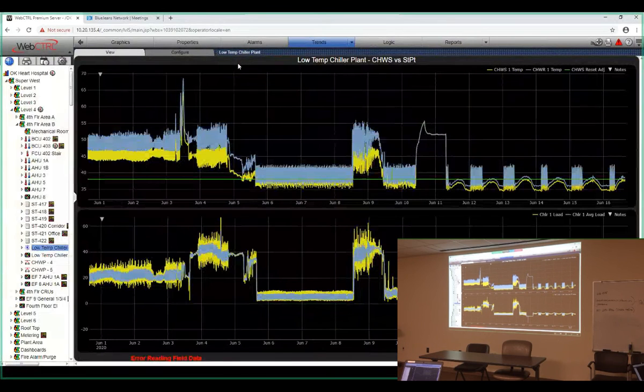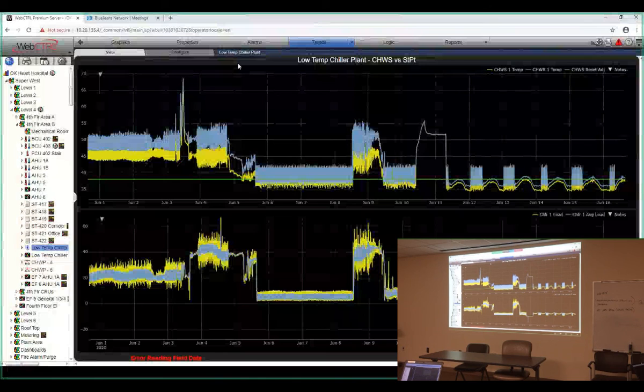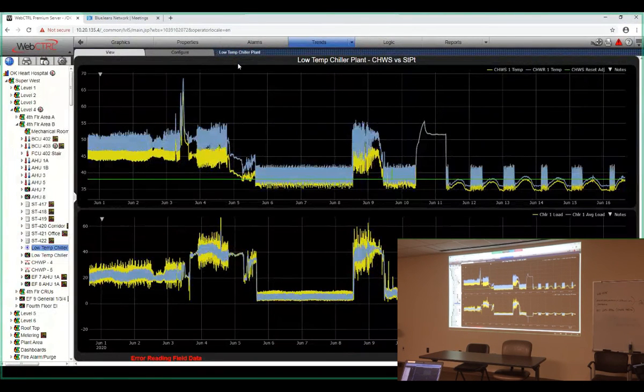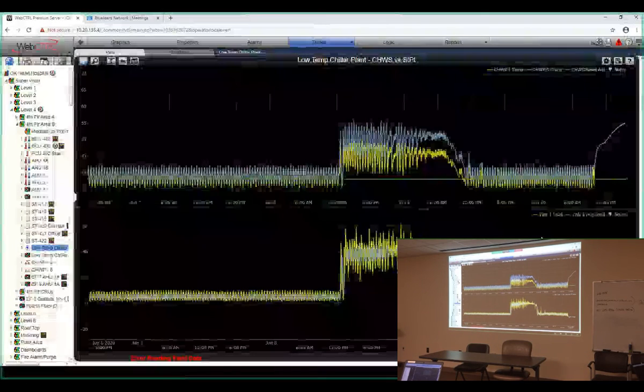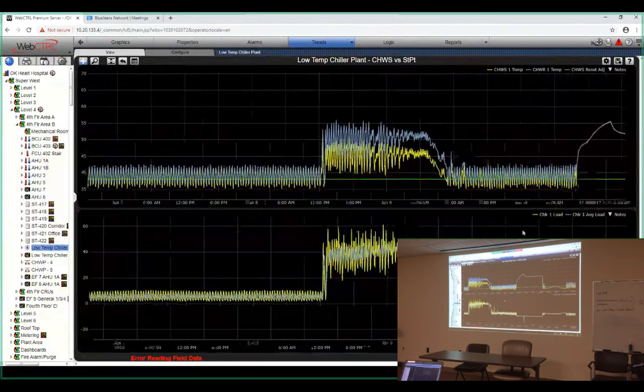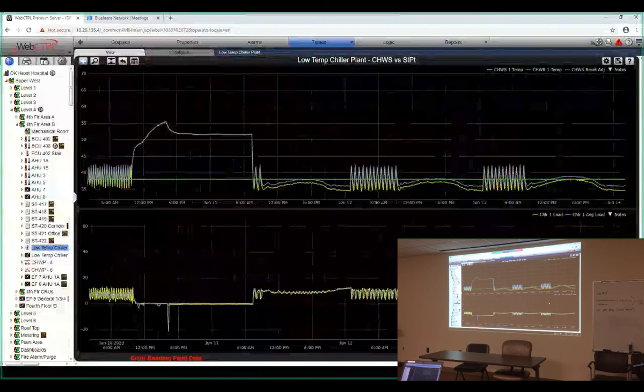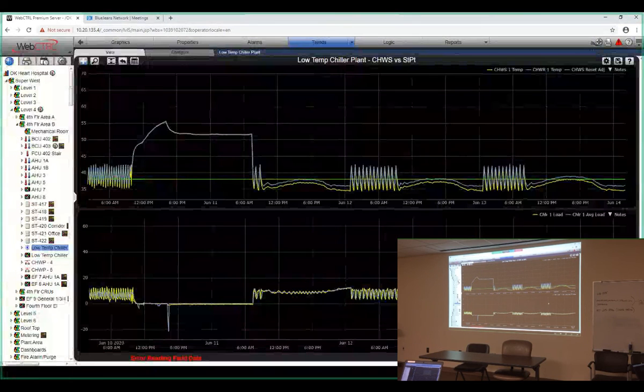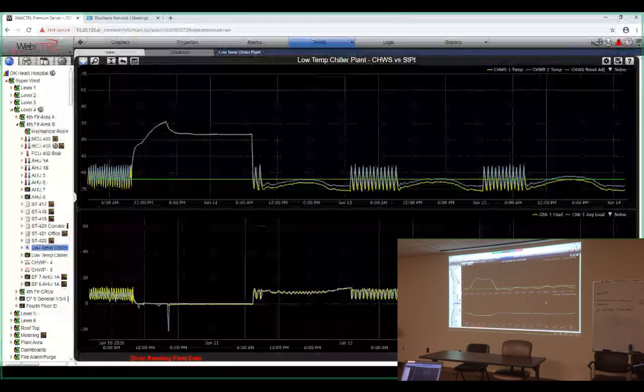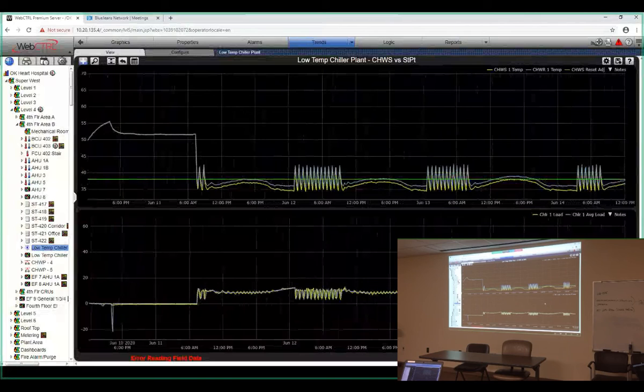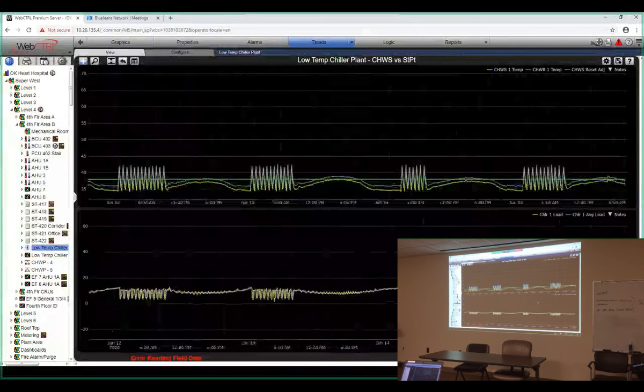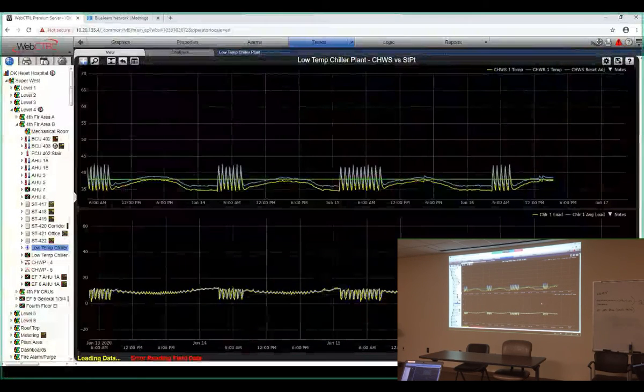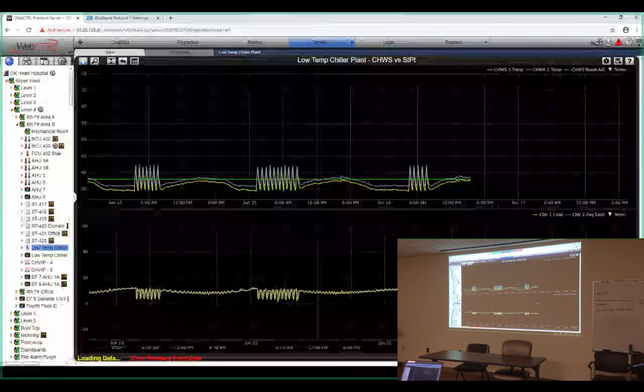It's pretty neat. It's a good place that I can build, since we're only having to control one coil here, we can actually create a trend that looks at both of those pieces of equipment at once. Go back and look at what the air handler is doing at that same time on that low temp deck. I'll create that trend for you so we can see what's actually happening, because the load's dropping out. It's right there in the middle of the night too, isn't it? 3 a.m. to 6 a.m. Or 9 a.m. Just drop it in.